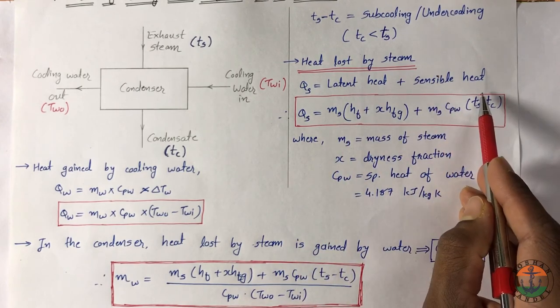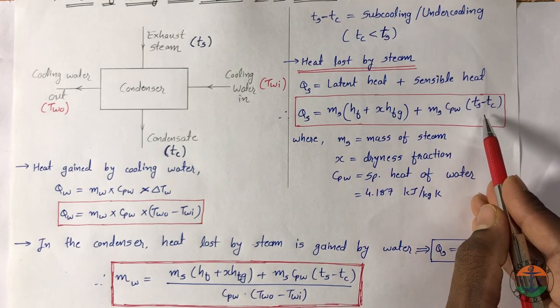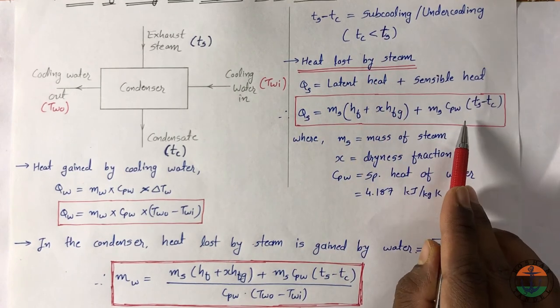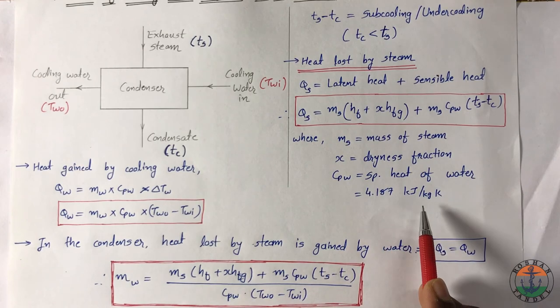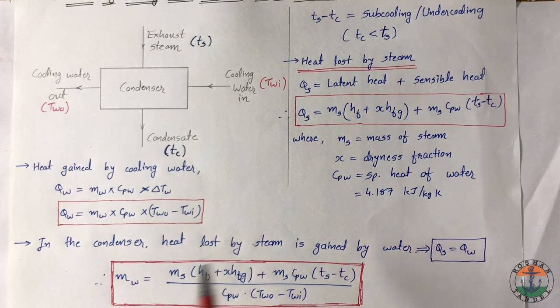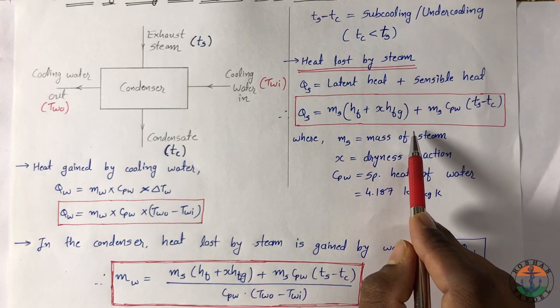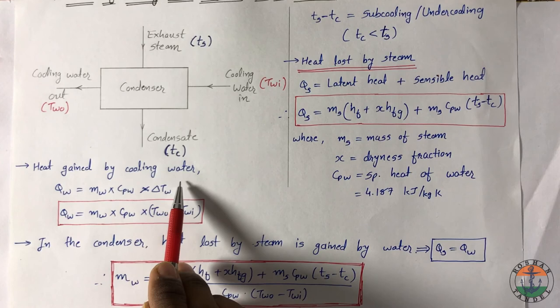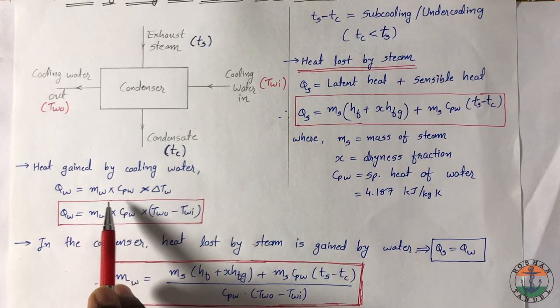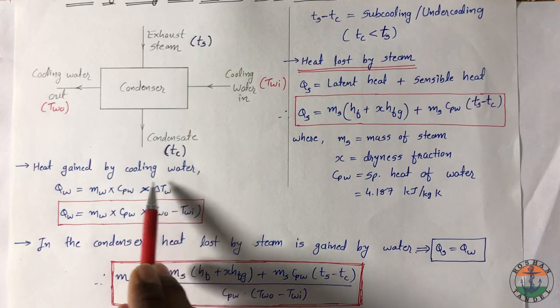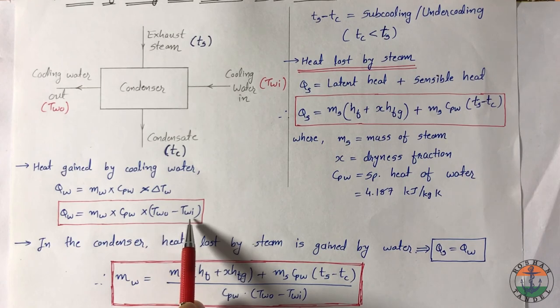Sensible heat is calculated by M Cp into delta T, here delta T you have to take subcooling. Cpw is the specific heat of water which is 4.187 kJ per kg kelvin. This much amount of heat is lost by the steam, which is gained by the cooling water. Heat gained Qw is calculated by M Cp into delta T for water. Delta Tw is equal to Two minus Twi.